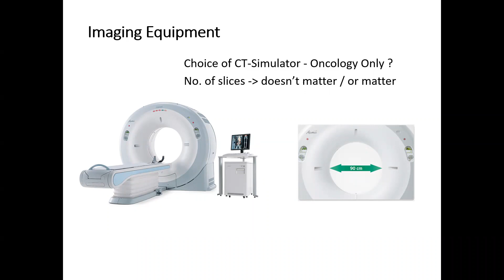Imaging equipment, all these things written on the left side of this picture, basically everyone knows very well about that, but I'm just going to share some tricks and tips. The compatible tabletop: the tabletop should be fully compatible with the linear accelerators. Sometimes it becomes very difficult. For example, in my center, we have 5 linear accelerators and 2 dedicated CT simulators. The couch tops of 4 of the linear accelerators are compatible with 1 of the CT scanners, and 1 linear accelerator has a different couch top, and then the second CT simulator has a different couch top. So sometimes we end up with issues like that.